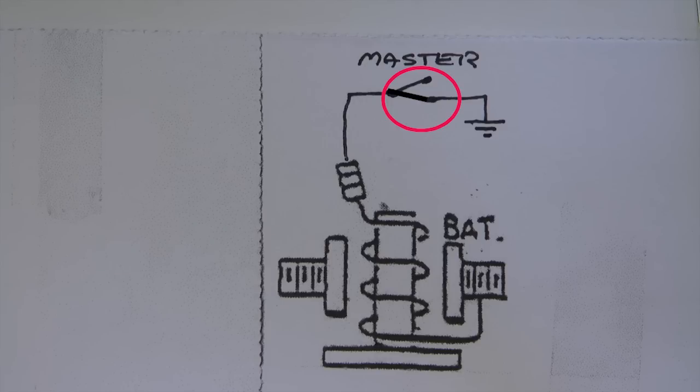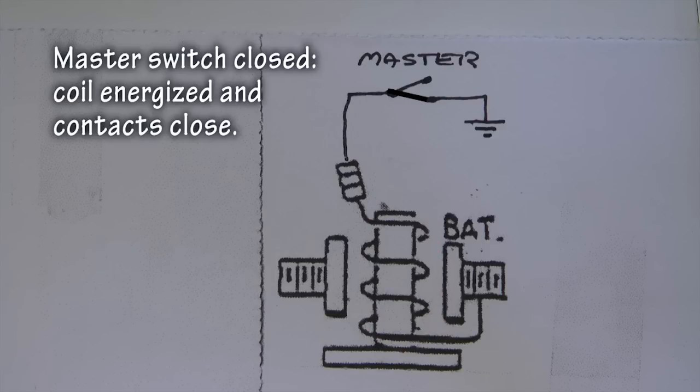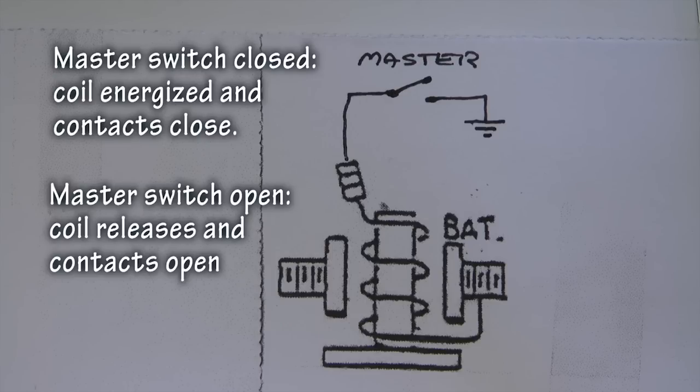We are supplying power to an internal coil. This coil is an electromagnet that pulls our large contacts closed and keeps them closed as long as we keep the coil energized. When we turn off the master switch, that magnetic coil stops pulling and an internal spring returns the contacts to the open position.